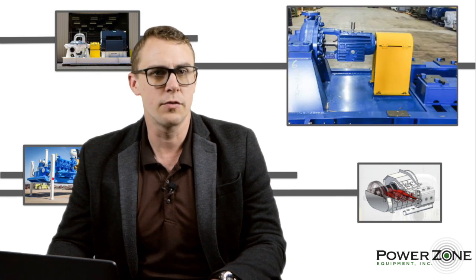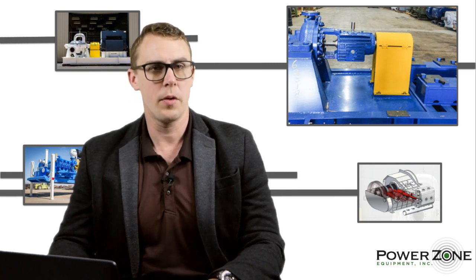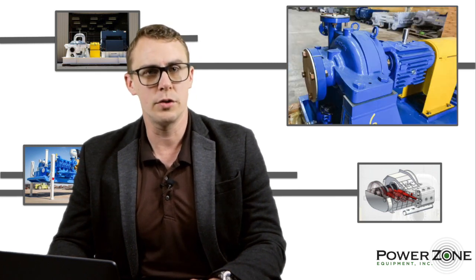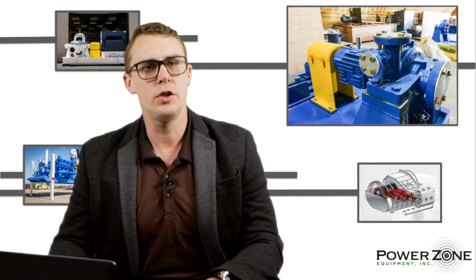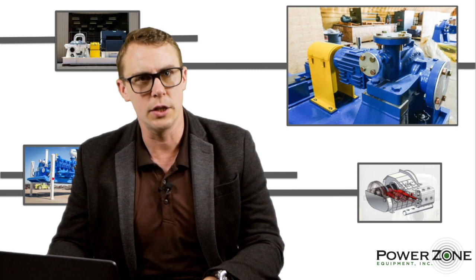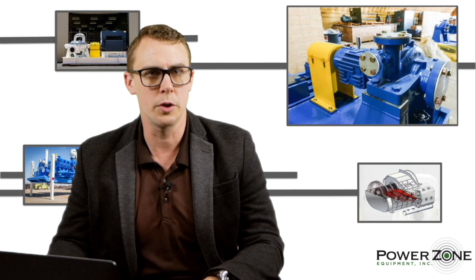A base plate, S-4 case material. It is a single stage with an 11.125 inch impeller, 4 inch, 300 pound suction flange, and a 2 inch, 300 pound discharge flange. This unit is ideal for industrial applications such as cooling loops or dewatering, or can be used to supply charge pressure to a larger pump.